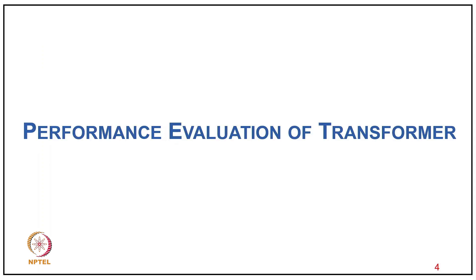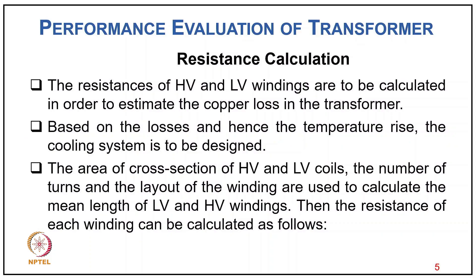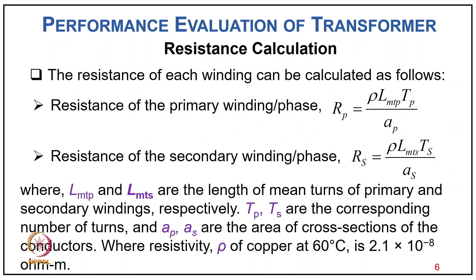Coming to the performance analysis of transformers, the resistance of high voltage and low voltage windings are to be calculated in order to estimate the copper loss in the transformer. Based on the losses, the temperature rise and the cooling system is to be designed. The cross-section area of HV and LV coils, number of turns, and layout of the windings are used to calculate the mean turn length, from which the resistance of each winding can be calculated.